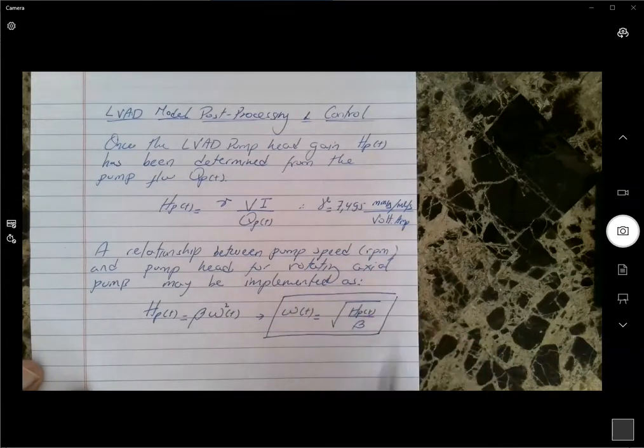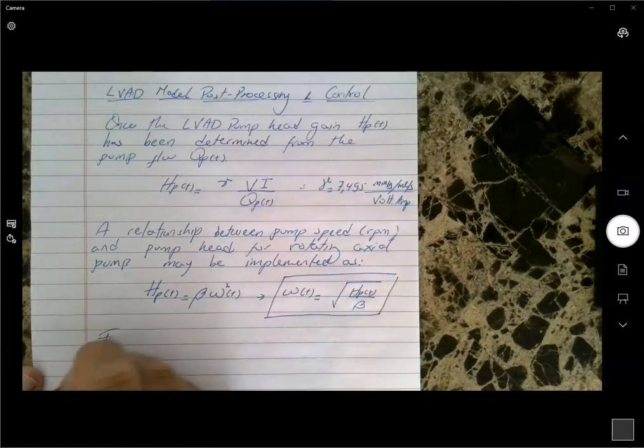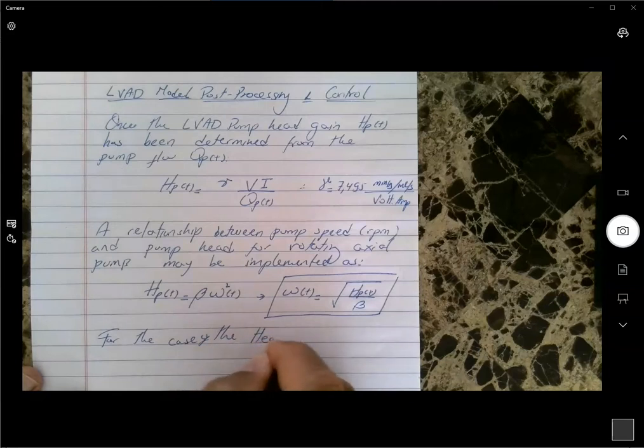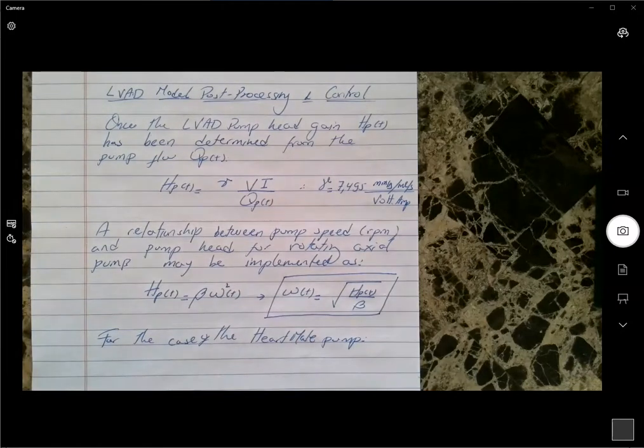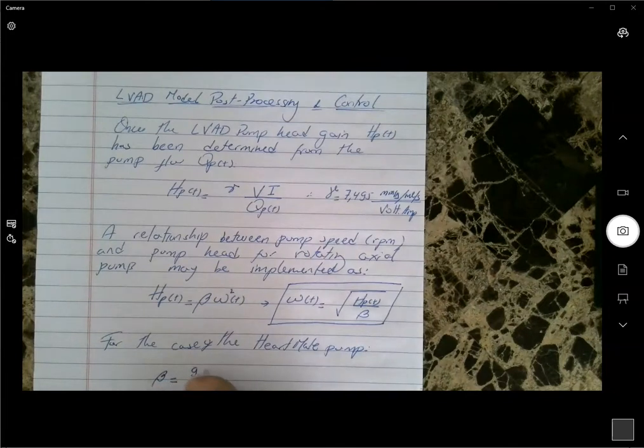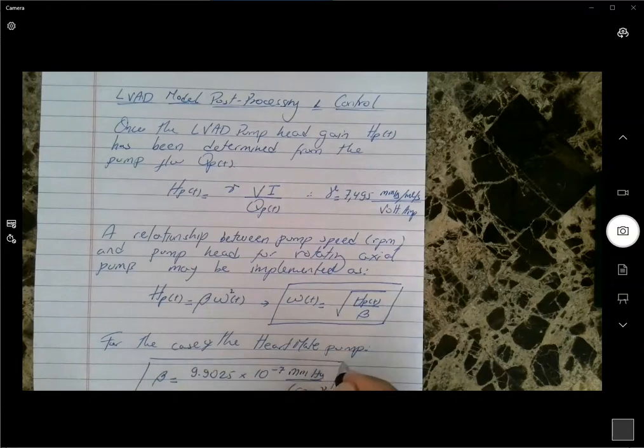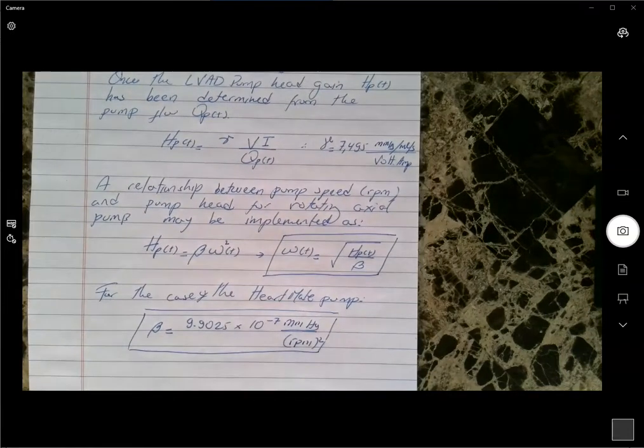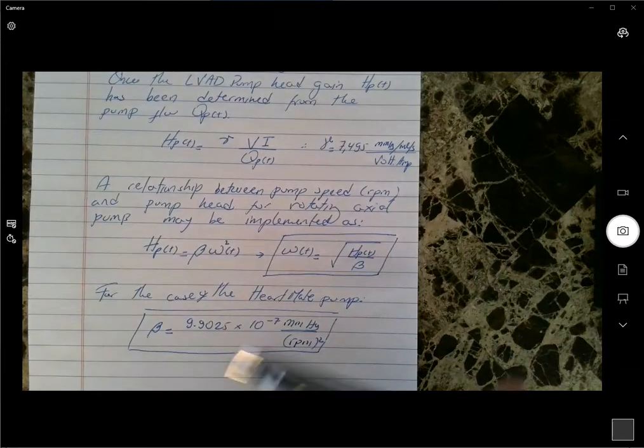So where this beta, for the case of the HeartMate pump, which is one of the most widely used axial flow pumps, beta is equal to 9.9025 times 10 to the minus 7 millimeters of mercury divided by RPM squared. So we can directly calculate the RPM from here.